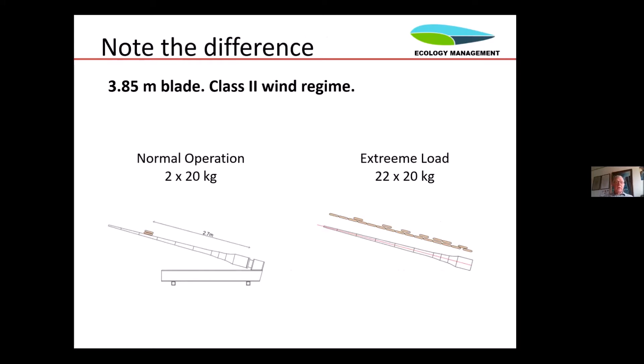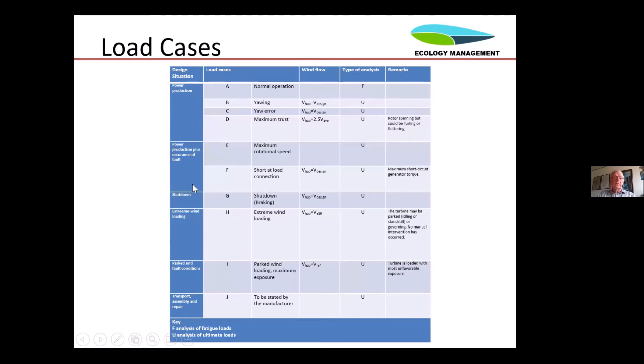For example, with a 10 kilowatt turbine with a 3.85 meter blade made of organic fibers, normal operation gives a load of 40 kilograms at 2.7 meters out. That's not much, but that's not how we design the blade. The blade has to be designed for the extreme load, which is actually 440 kilogram-force distributed over the blade. The extreme load is something you have to find, and the Dash 2 standard is very helpful on how to calculate it. All the load cases are given, and there are not that many to consider.